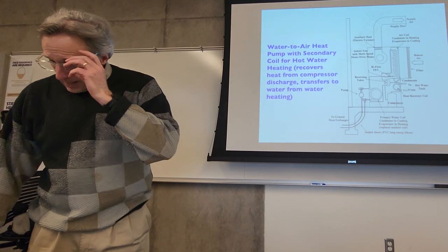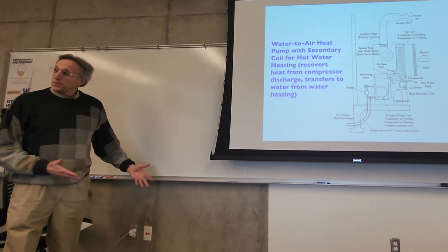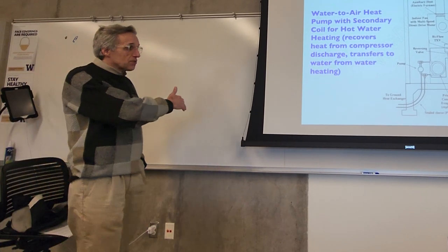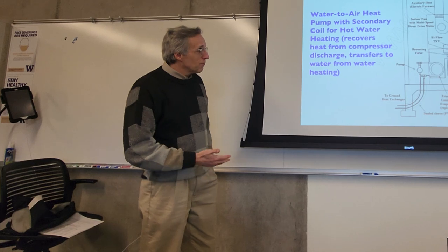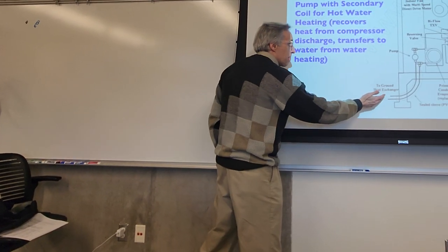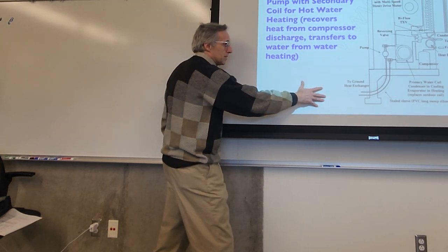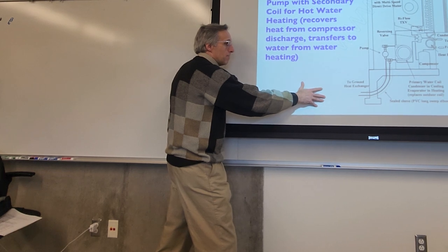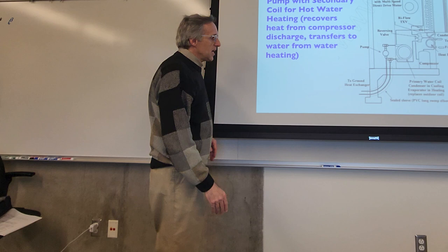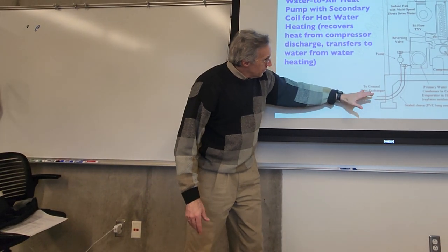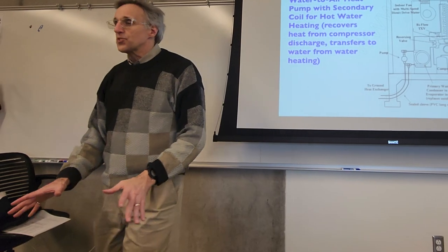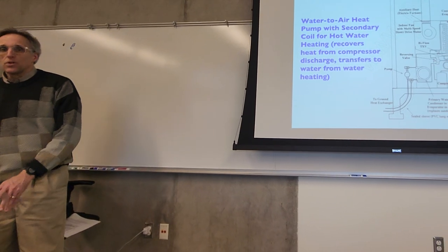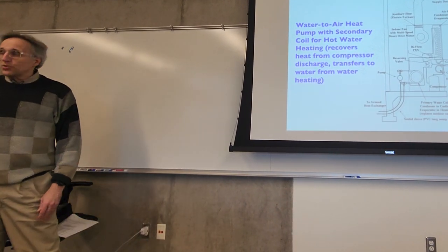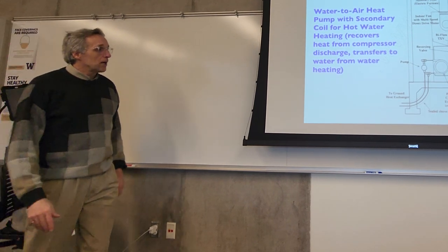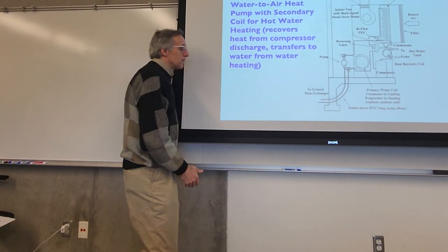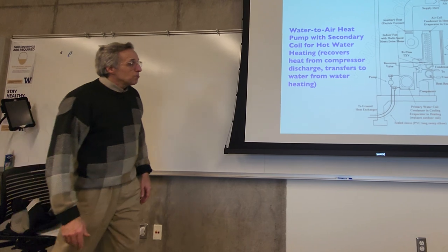And then we have, what do we have here? Oh, and then you get into what 21 Acres has, where we just saw it. The previous slide was an air-to-air heat pump. Now here we have a water-to-air heat pump, where our thermal sink isn't the air now, but it's actually the ground. These are much more efficient systems because the ground stays at a constant temperature, whereas the air temperature is always changing, and as the outside air temperature changes, the COP is changing constantly with an air source heat pump. This one you've got 50 degrees plus or minus a few degrees year round.